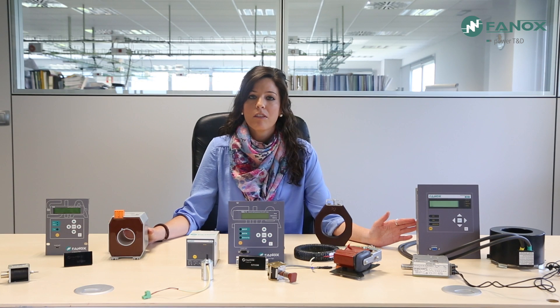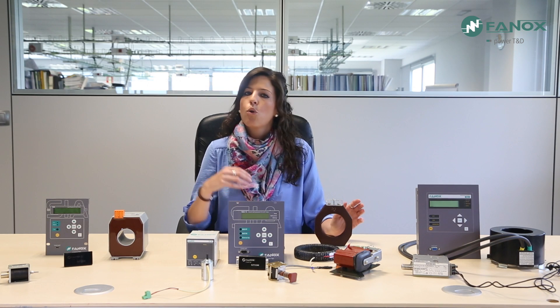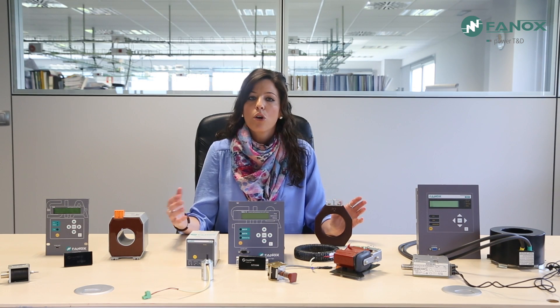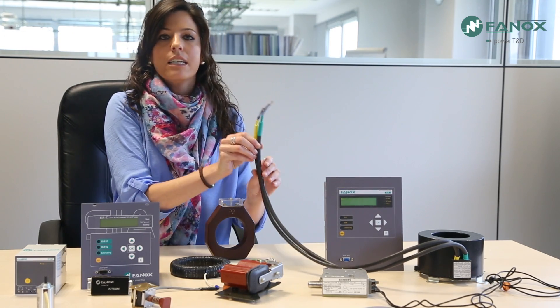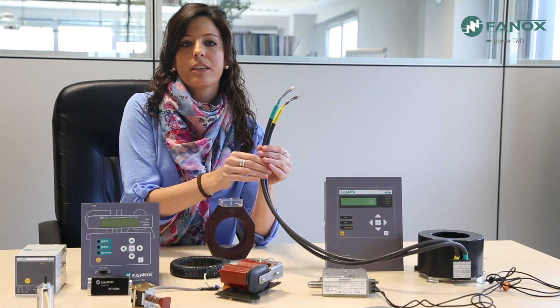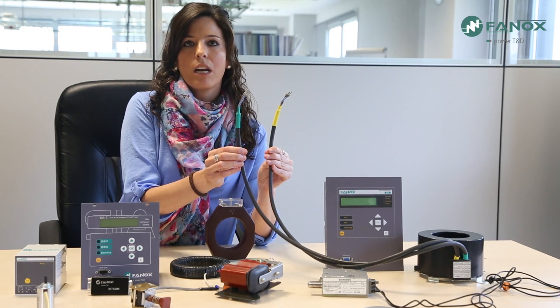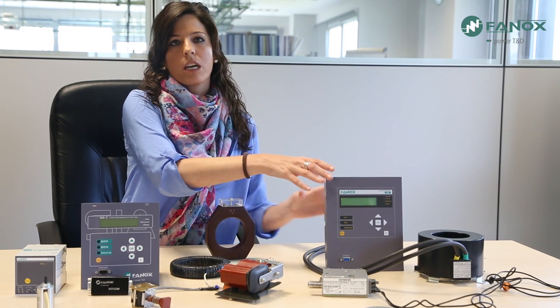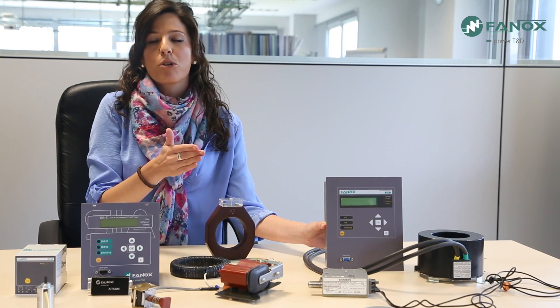The other group of Fanox self-powered relays works with specific transformers. Specific transformers provide special characteristics compared to standard transformers — for example, a higher saturation level, a wider measurement range, or a double core. In this group, the SIAA relay stands out. The SIAA relay works with double-core transformers, meaning these transformers have two separated cores with different materials. This allows one core to be used for measurement and the other for self-powering. As a result, the Fanox relay can start up from very low current — approximately 4 Amperes.